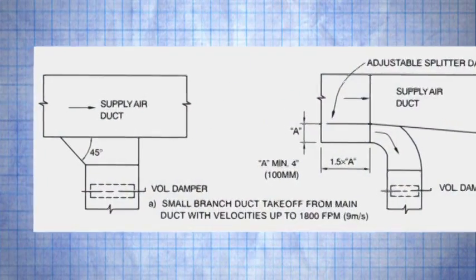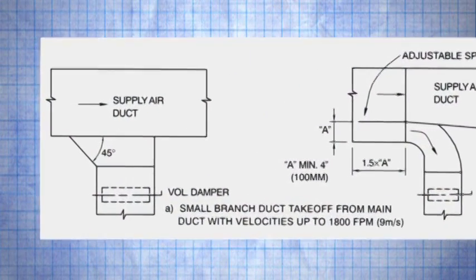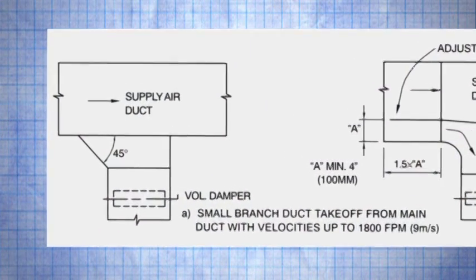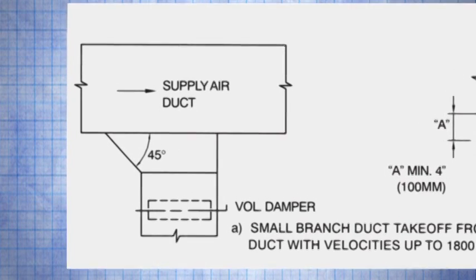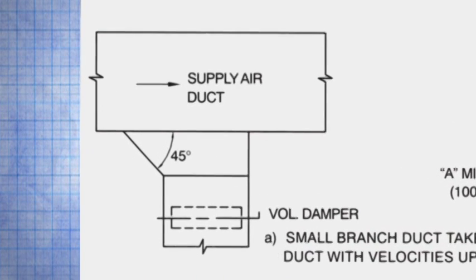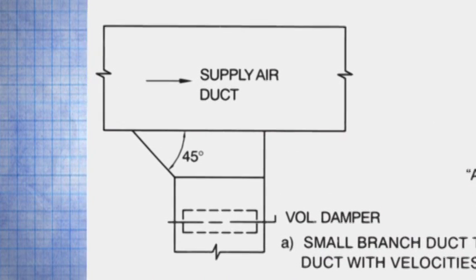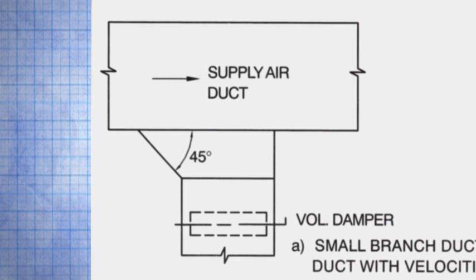One additional design point to consider is that if the damper is close to the main duct, the axis of the damper blade should be parallel to airflow. Otherwise, the scoop effect may cause a very small movement of the damper blade to impose a large difference on airflow changes, which makes air balancing problematic and less precise.